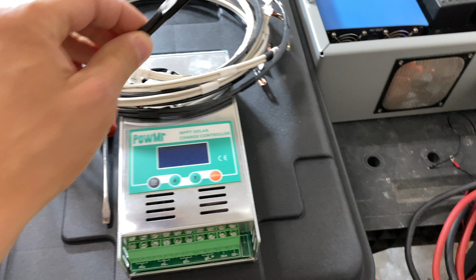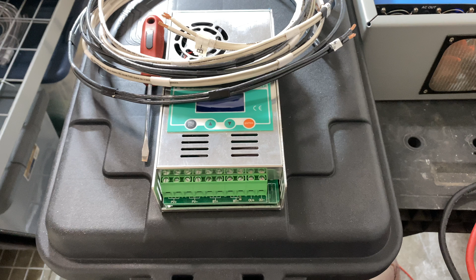To make all these connections I'm going to use doubled 10 gauge wire. One 10 gauge wire is supposed to handle 30 amps, so two of them should handle 60 amps. I'm going to connect two wires for PV positive, PV negative, battery positive, and battery negative.